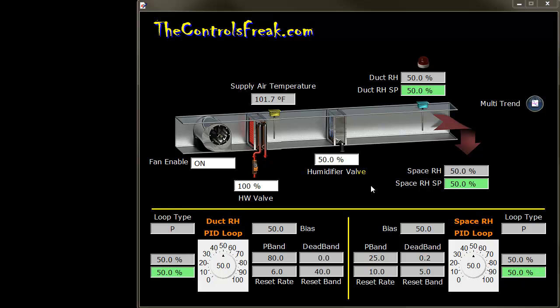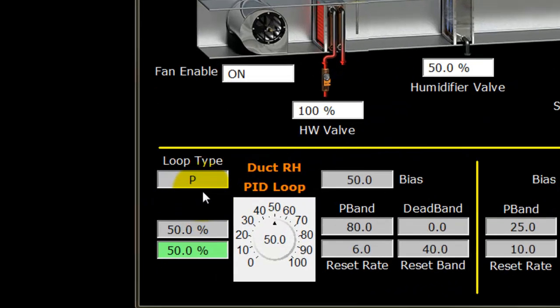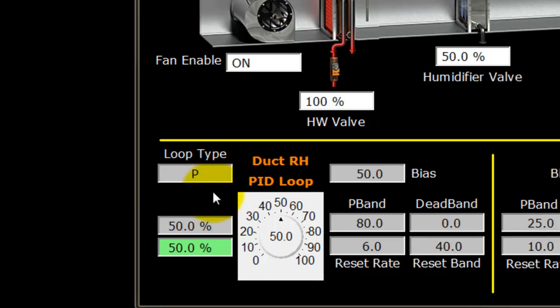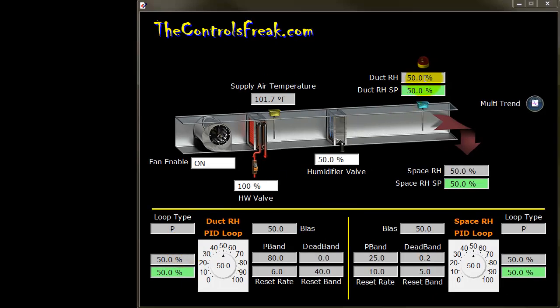While playing with the PID loops in those ICU rooms, I thought it would be a great opportunity to share how PID loops work and how I tune them. In this video, we're not going to talk much about the actual system, but more importantly we're going to look at the different parts of the PID loop — specifically the first type, which is the proportional-only loop. For a PID loop you need two pieces of information: an input, which here is the duct relative humidity, and a setpoint.